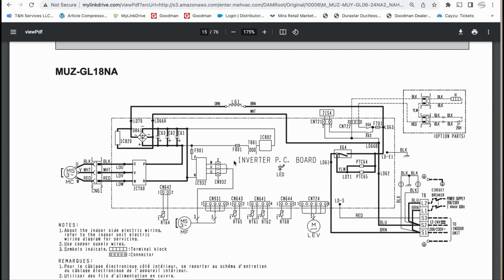We've got a couple other fuses on that board. We have fuse 901, and what that's going to do is feed the fan motor, right? So if we didn't have voltage at the fan motor, we'd check that fuse 901. Okay. So that's pretty much it on the wiring diagram. And then there's another fuse, and that's fuse 801. But anyway, so that's that.